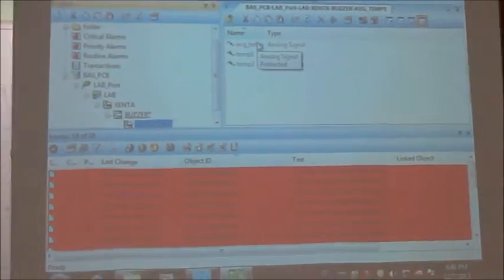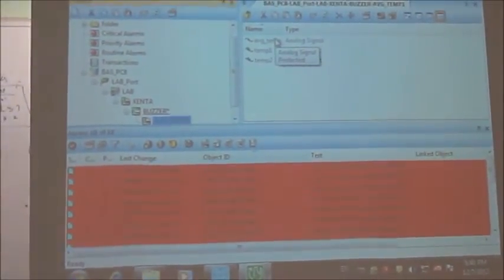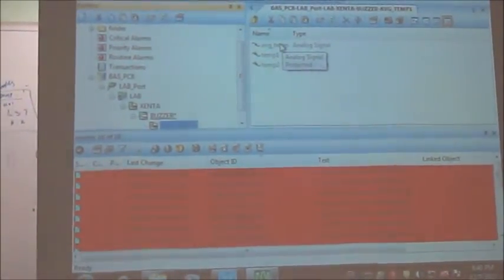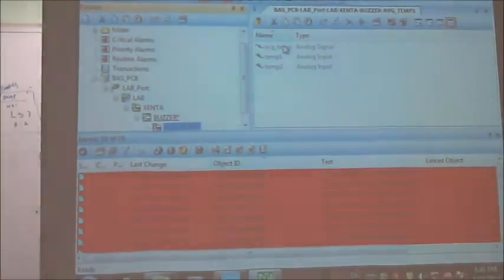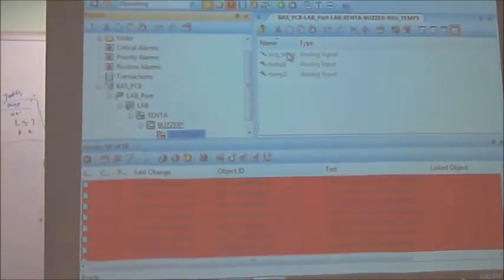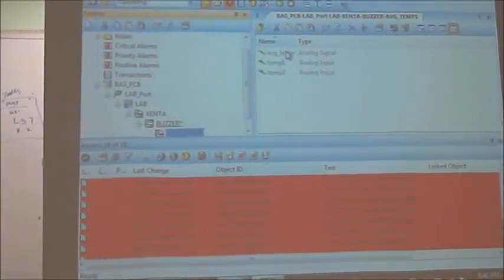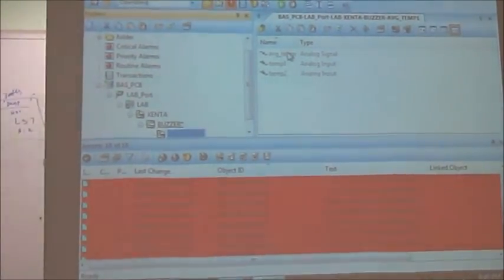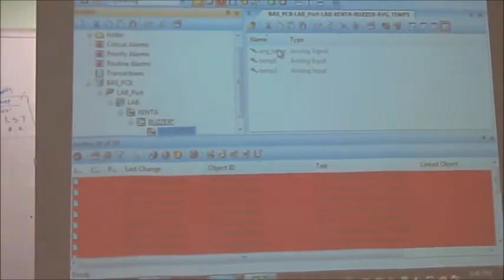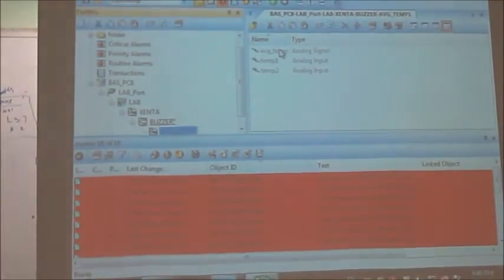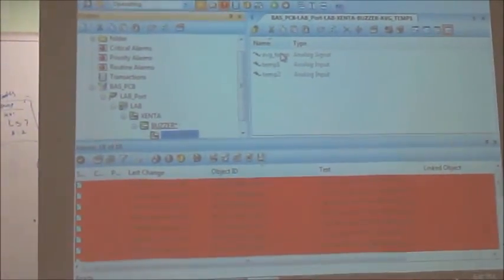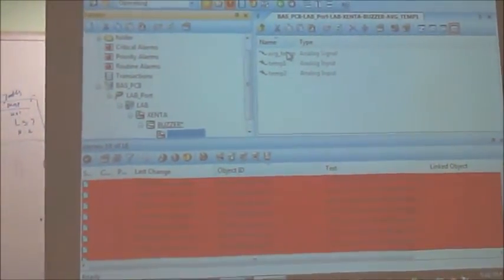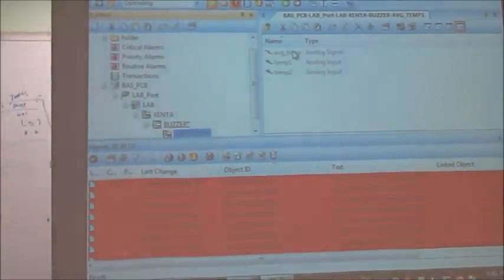here. It means those blocks, if you want to view them from here, for example, on a day-to-day basis, like a set point, you want to change your set point, sometimes maybe 21, sometimes 22 degrees, every time I need to download. This is not so intelligent. What does it mean? Every time I need to download my controller, how many times do I need to change the controller? So normally we make it public, then we can just change it from the workstation.